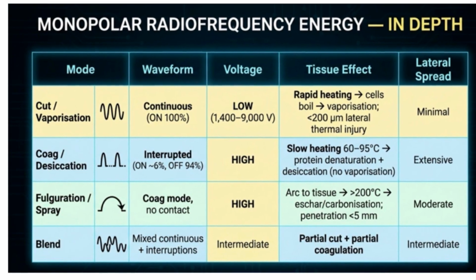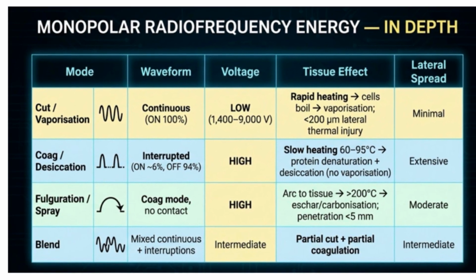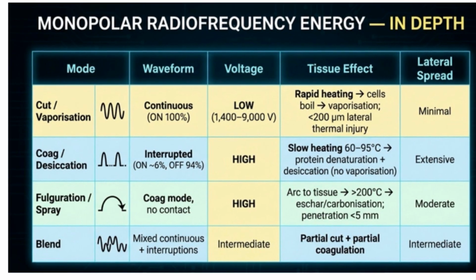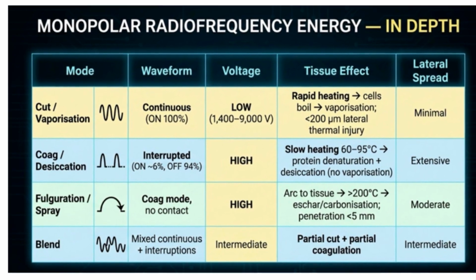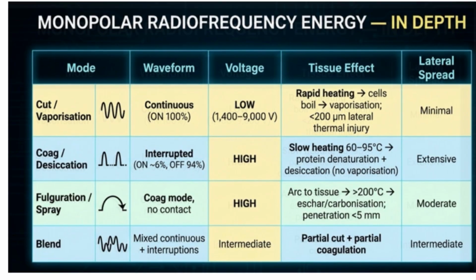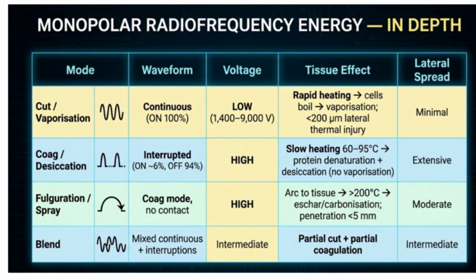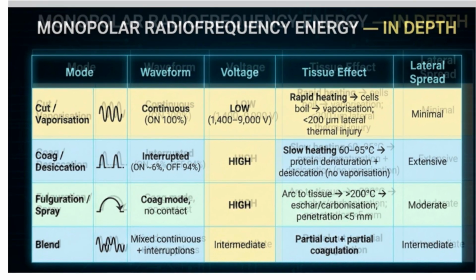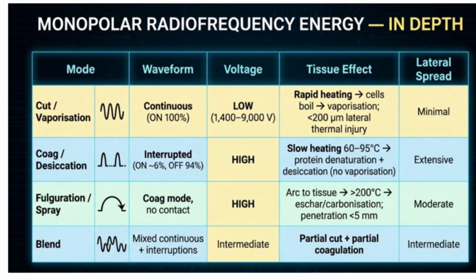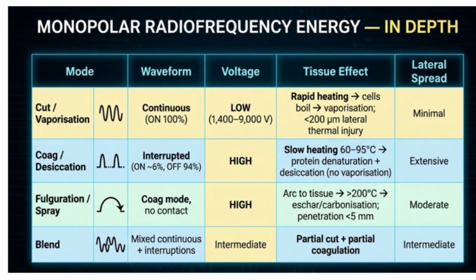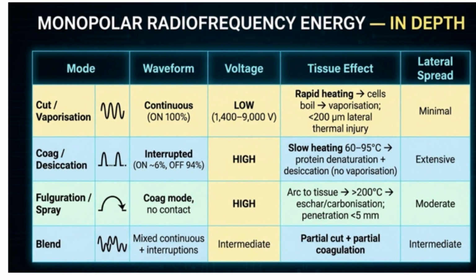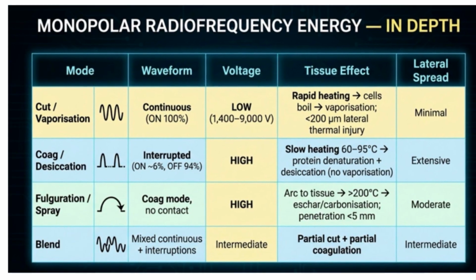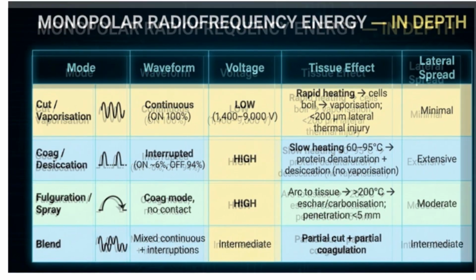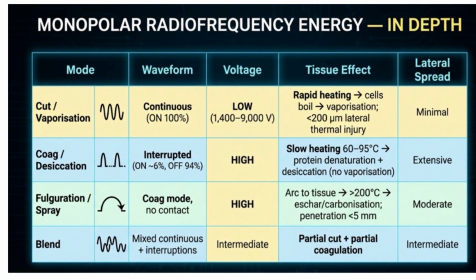In coagulation, the current is interrupted. It is high voltage. There is slow heating, 60 to 95 degrees, and protein denaturation plus desiccation. No vaporization occurs here. It is extensive lateral spread. Fulguration is the coagulation mode. No contact, higher voltage. There is an arc to the tissue, more than 200 degrees centigrade. There is eschar or carbonization. The penetration is less than 5 mm. The lateral spread is moderate.